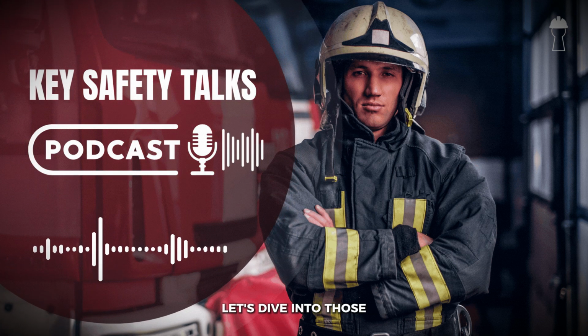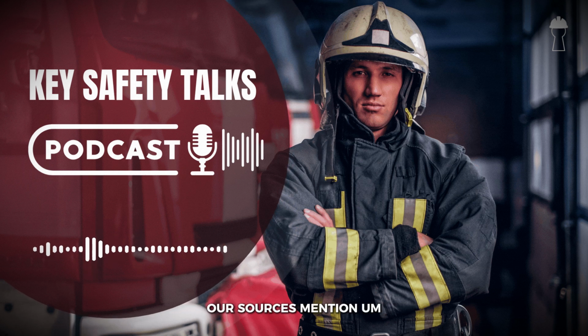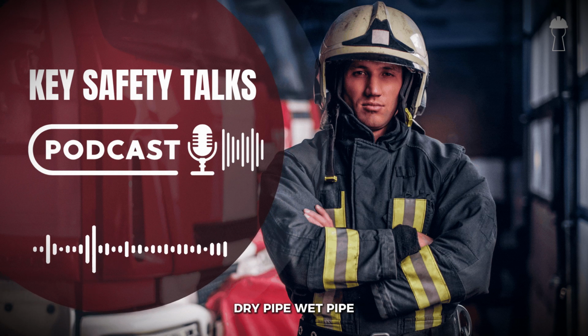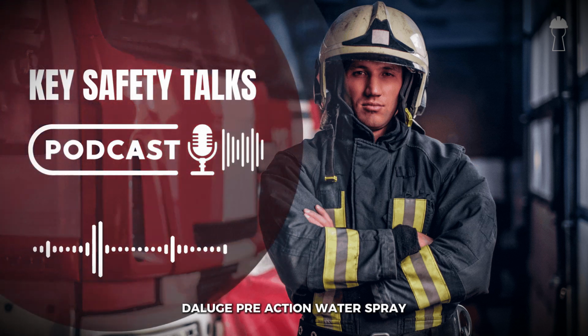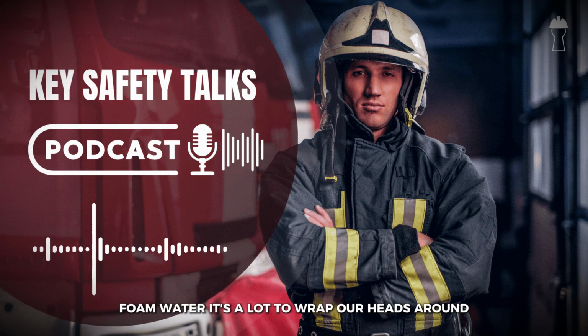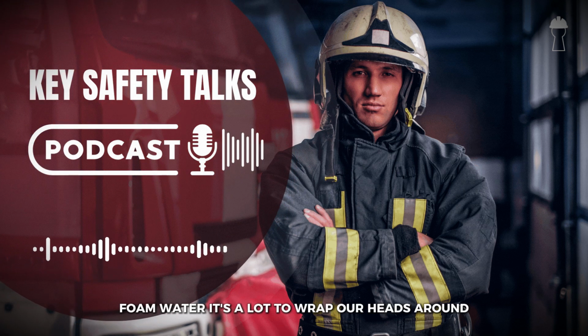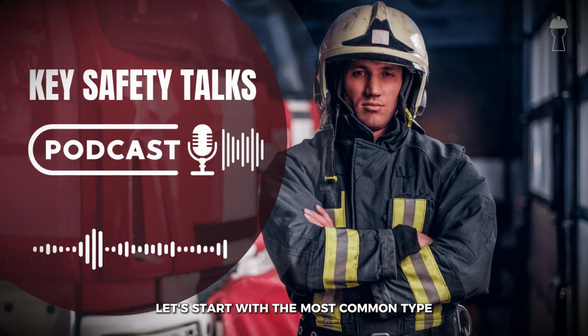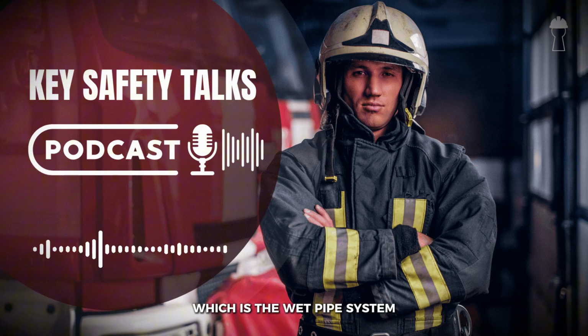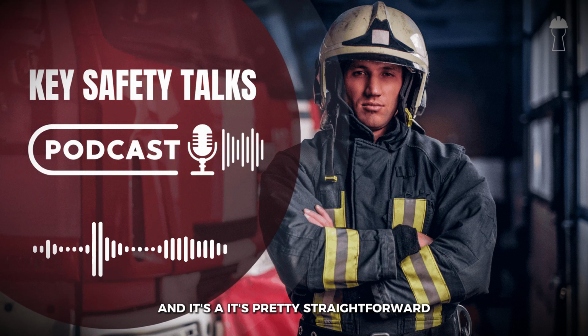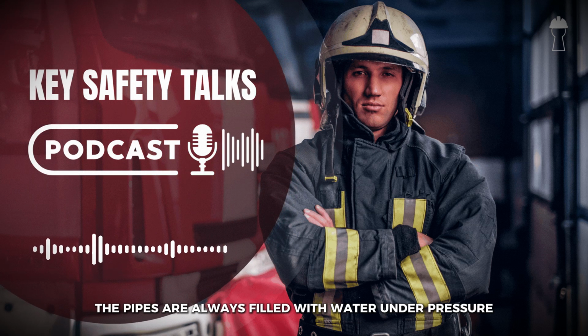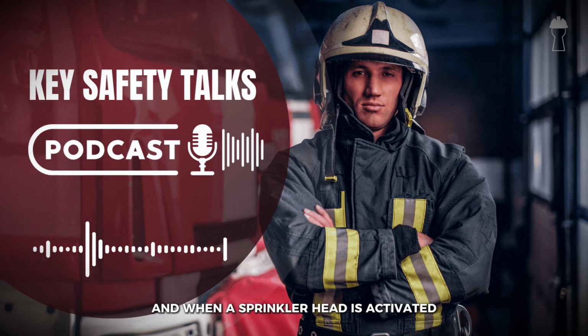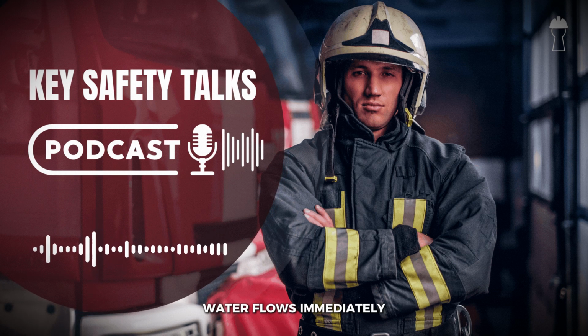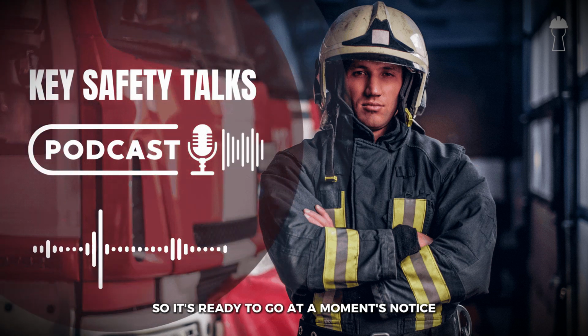Okay, so let's dive into those different types of sprinkler systems. Our sources mention dry pipe, wet pipe, deluge, pre-action, water spray, foam water. It's a lot to wrap our heads around. Where should we start? Well, let's start with the most common type, which is the wet pipe system. And it's pretty straightforward. The pipes are always filled with water under pressure, and when a sprinkler head is activated, water flows immediately. So it's ready to go at a moment's notice.